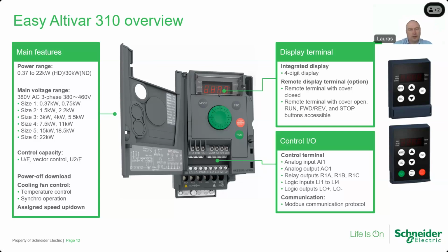As I said, it can control pumps and ventilators. Also, it can control constant torque applications. It also has a braking module on board, and you can connect a braking resistor. You don't need an additional module, so you may have dynamic braking with a braking resistor.